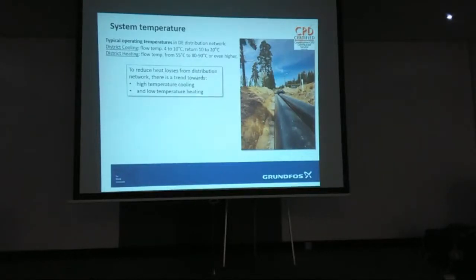Anyway, right, so what people are trying to do is increase the temperature on cooling and lower the temperature on heating. So if you've got an energy centre chucking out, I don't know, not as low as 55, I don't think, in our world, probably 60 to 80 degrees, and it's coming back at 40 degrees, you've got a good operating system. It's what it's going to feed. So really, before you do an energy centre, you want to go to the other end and ask, are these radiators, air handling units, fan coils? What is it you actually do? Underfloor heating? If it's only underfloor heating, you can get away with 55 degrees, easily, and then bring it down, because if this floor was 55 degrees, it would be too hot.